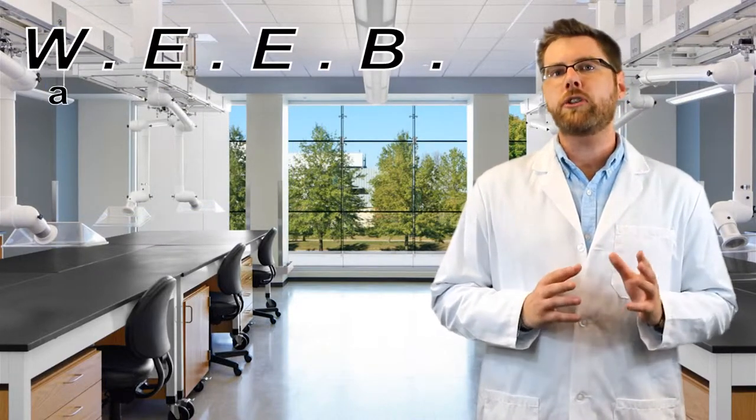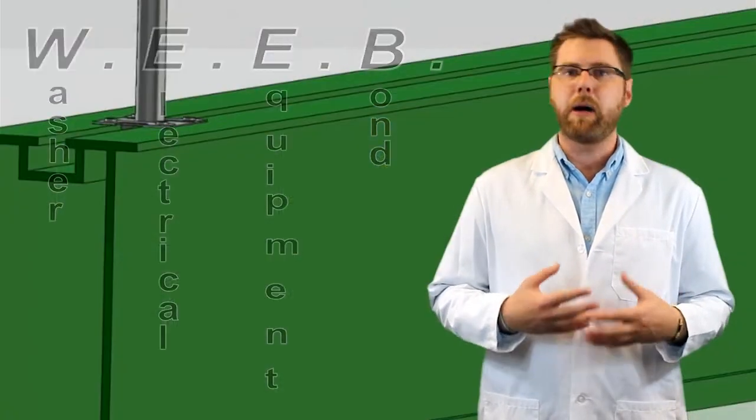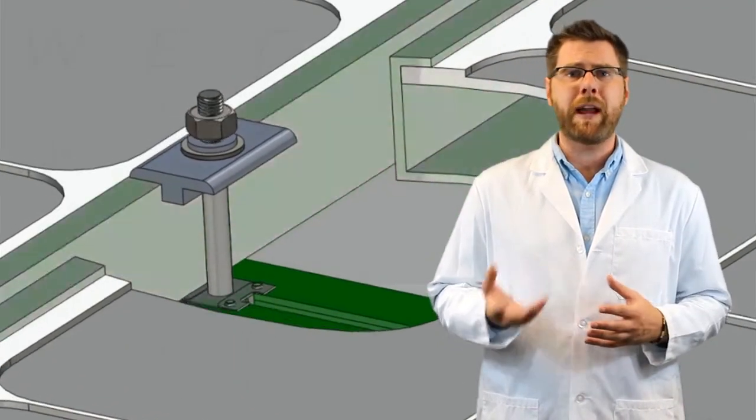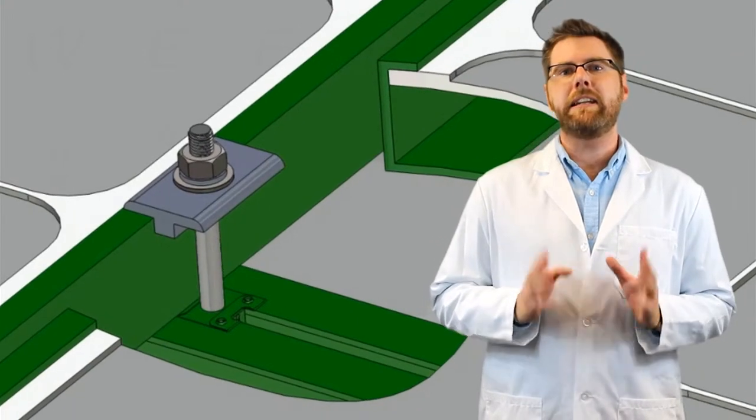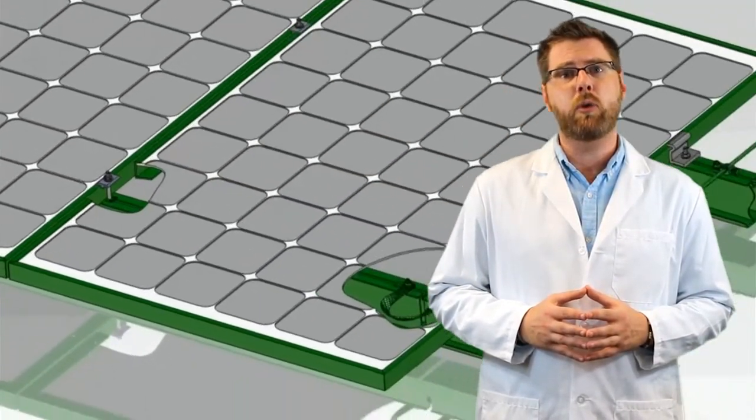WEEB stands for washer-electrical equipment bond. It's a device that can be used to bond or electrically connect together all the separate metal pieces in a PV array - your modules and your rails. This allows significantly less copper wire to be used in connecting your system to earth ground.